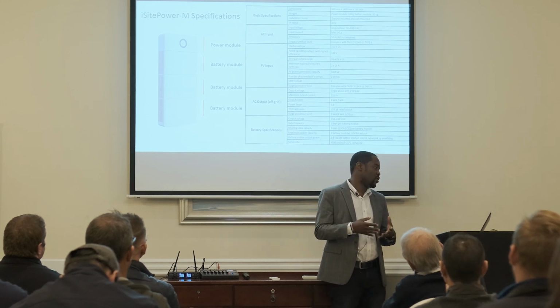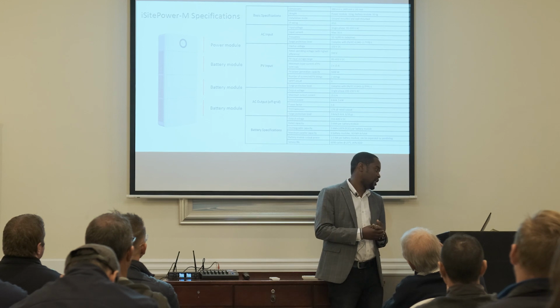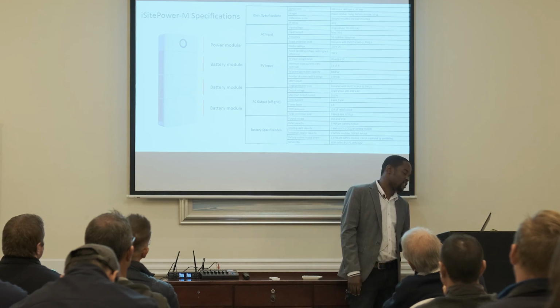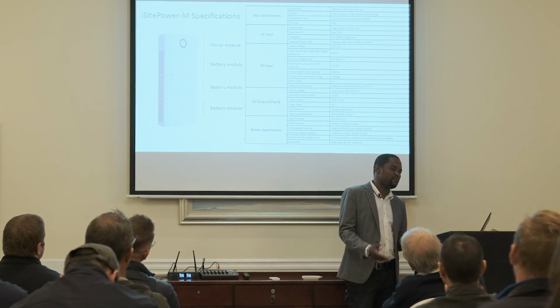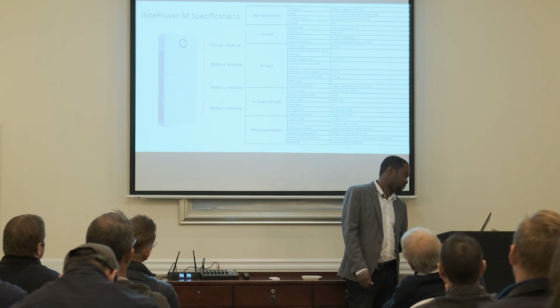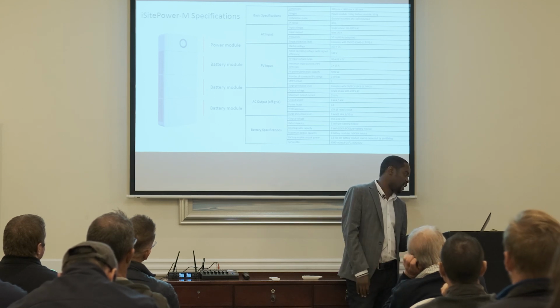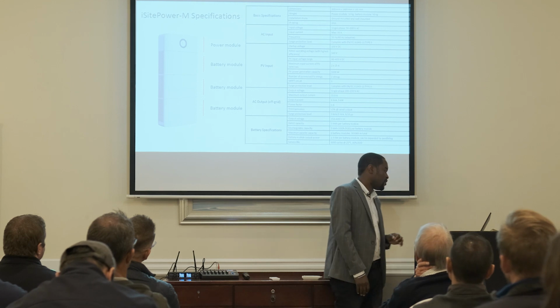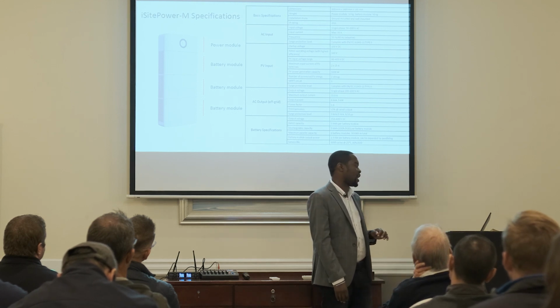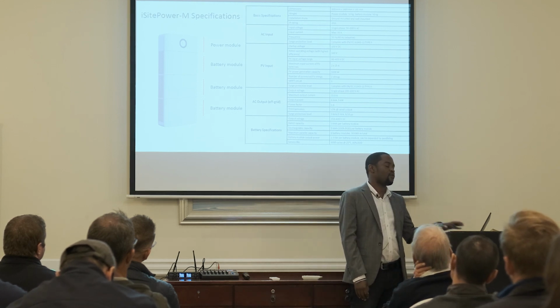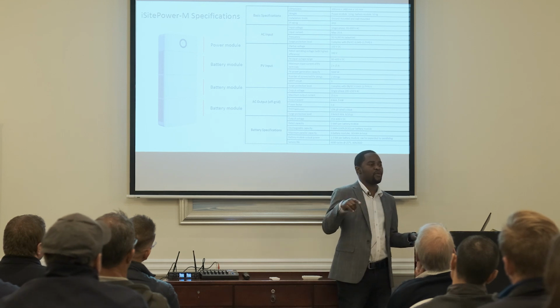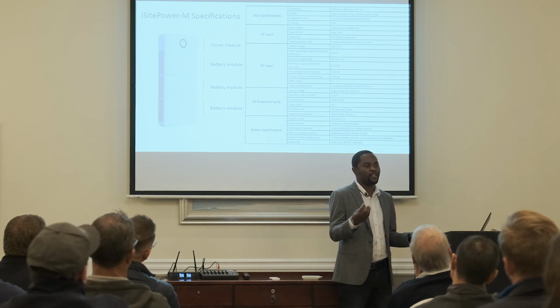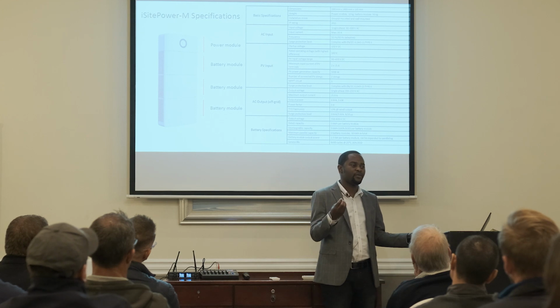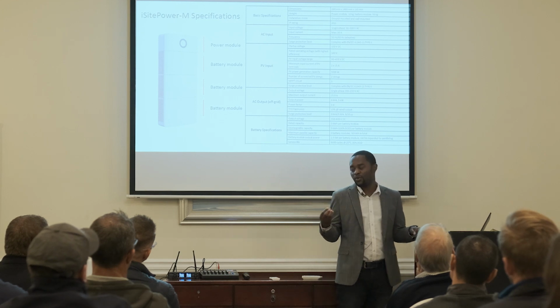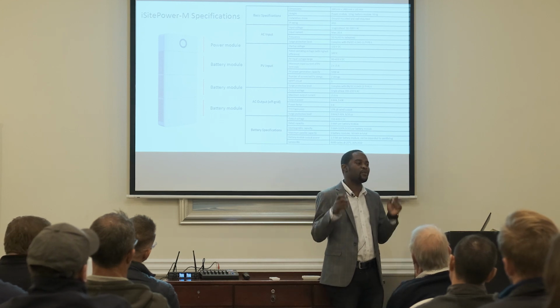Those harmonic distortions on the Huawei system are less than 3% at rated output, as you can see. So the distortions you are getting are minimal and very small in magnitude. So you are guaranteed that even on off-grid, you are getting a pure sine wave. This is important when you are dealing with communications, where the purity of the sine wave matters. So this is not only giving you a power output, but what they call clean power.